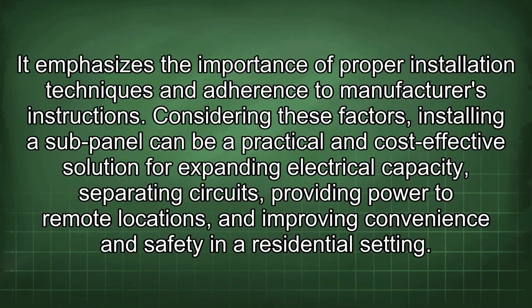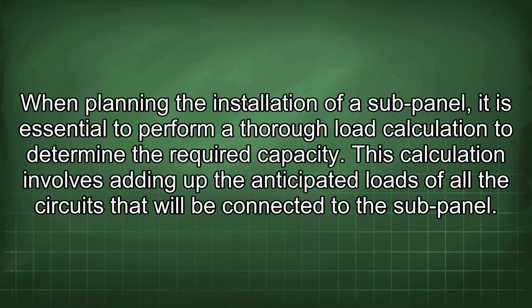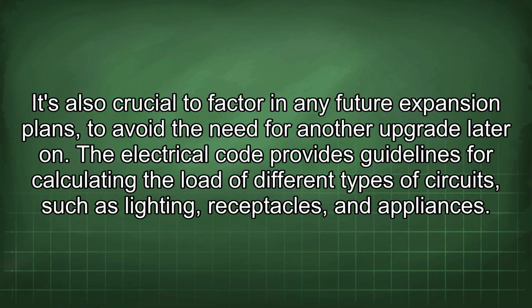Considering these factors, installing a sub-panel can be a practical and cost-effective solution for expanding electrical capacity, separating circuits, providing power to remote locations, and improving convenience and safety in a residential setting. When planning the installation of a sub-panel, it is essential to perform a thorough load calculation to determine the required capacity. This calculation involves adding up the anticipated loads of all the circuits that will be connected to the sub-panel. It's also crucial to factor in any future expansion plans to avoid the need for another upgrade later on.